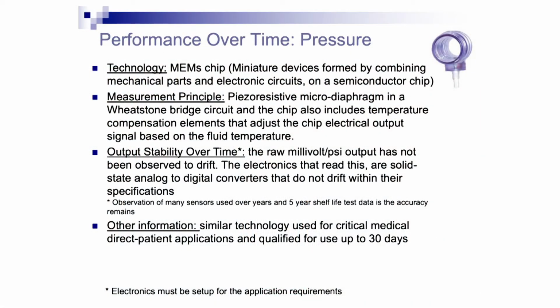I'll kind of bounce through these, and I can provide more information afterwards if anyone wants to know more about the technology. But this is mainly to give you an idea of the durability of the technology doing the main sensing measurement. In our pressure sensors, there's what's called a MEMS chip, and it was one of the first MEMS technologies available on the market over 20 years ago. We've improved and refined it for bioprocess operations, and it's basically a micro diaphragm on a circuit that changes resistance, meaning piezo-resistive, as its pressure changes. And for stability over time, we haven't seen any observation of drift, and we have some data to back that up.